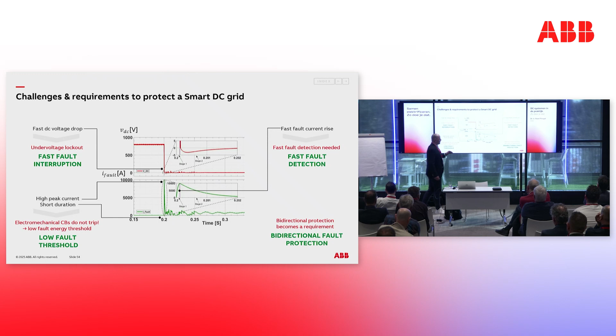So ideally, you want to cut off the short circuit current very fast, and this is where solid-state circuit breakers come in. Because if we use an electric arc to extinguish the short circuit current, we need tens of milliseconds. That's why in DC systems, especially those with more installed devices rather than just point-to-point connections, we move to using solid-state circuit breakers.